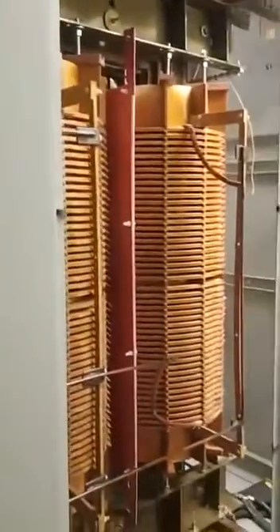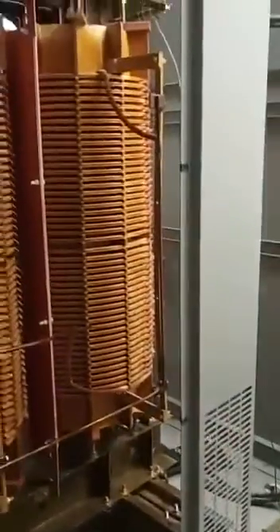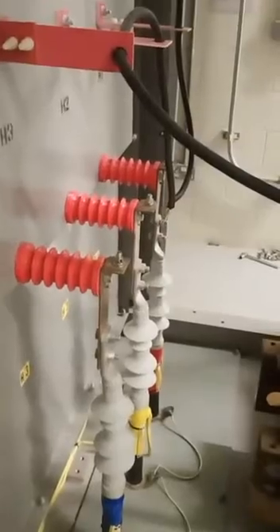Dear friends, in this video we are going to explain how to perform the IR test for the transformer. The transformer rating is 2000 kVA, a dry-type medium voltage transformer. This is the primary side of the transformer, 13.8 kV, delta connection. And this is the secondary side of the transformer, star connection, 400 volt.